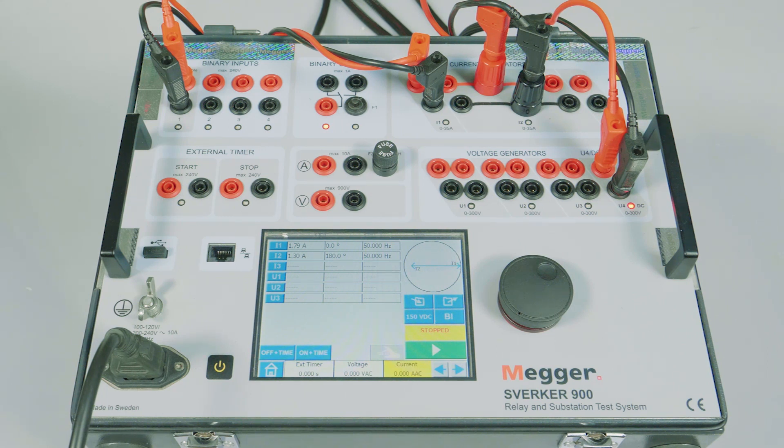The R-phase and Y-phase CT from the test kit are connected in parallel to the R-phase HV side in the relay, using the external superimposing method.